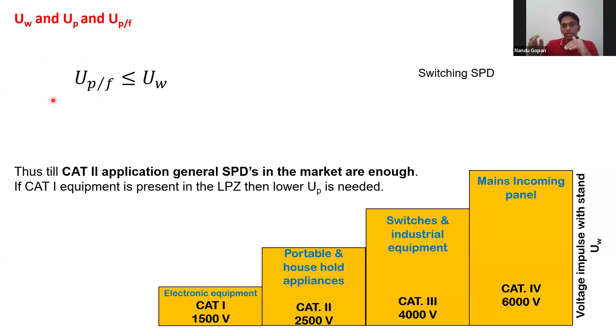UP by F is the voltage protection level, the impulse protection which you are going to provide for this equipment. So if the impulse which is going to come to the equipment is less than 2.5 kV, then it is protected. That is what it means. So this is how much protection you are going to give. UP by F is equal to UP plus delta U.